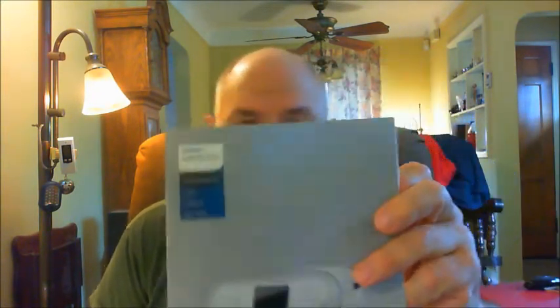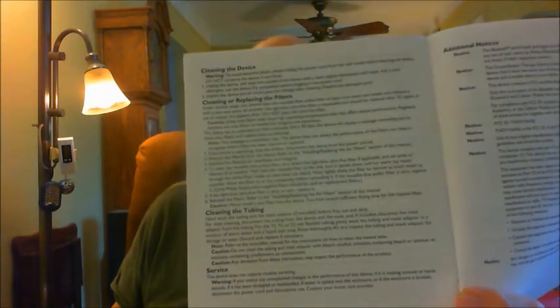But I want to preface this with the fact that this is the original manual brochure that came with this machine, and having looked through it, Philips says ozone is an unauthorized cleaning method for their machine. They're backing away: you used ozone, it's your fault. As I said, I got this machine 3 years ago along with this manual, and in the cleaning section there is no mention, not once, of a caution to not use ozone or ultraviolet. No, it's not in here.